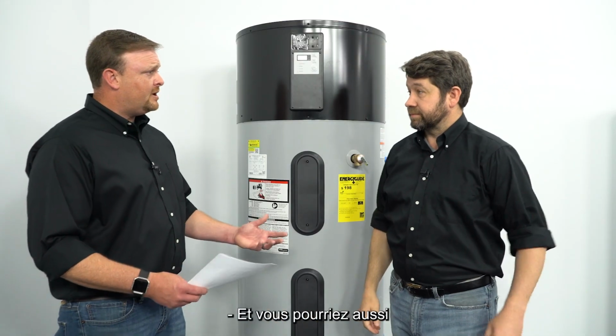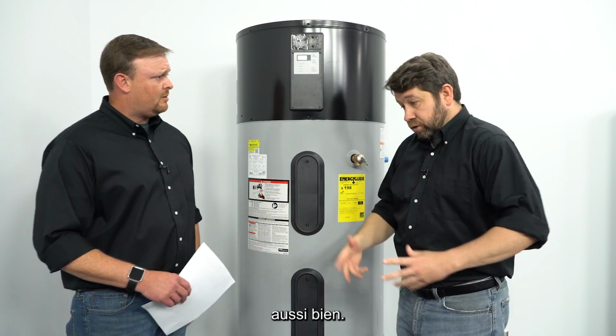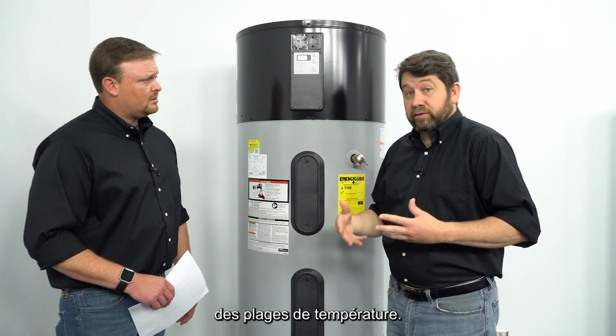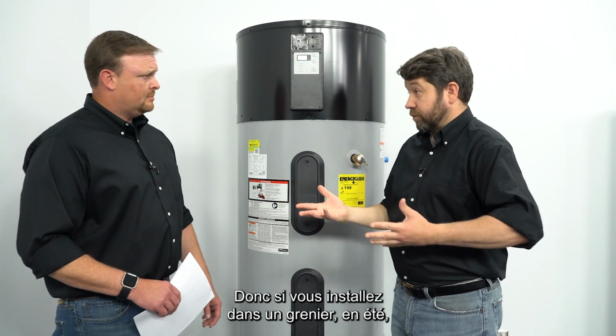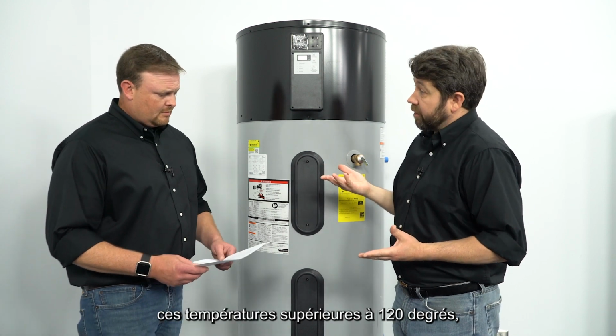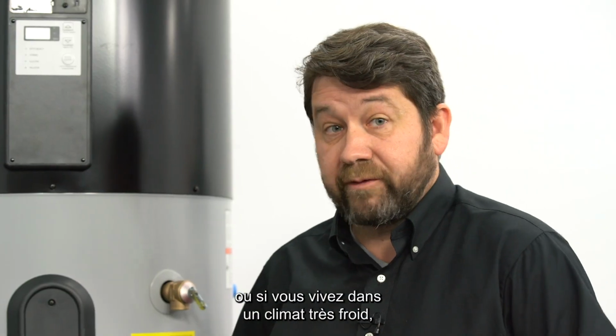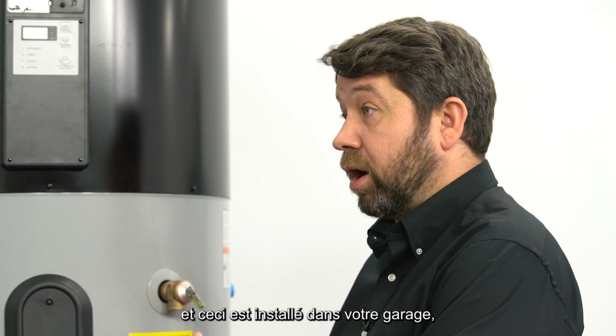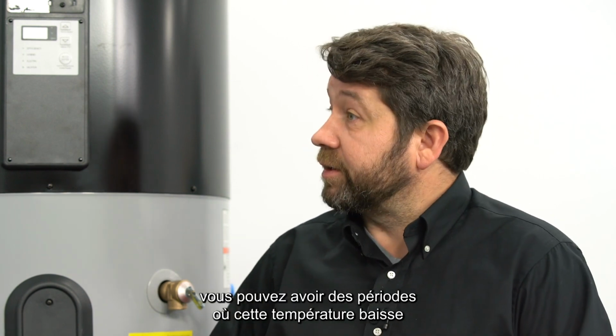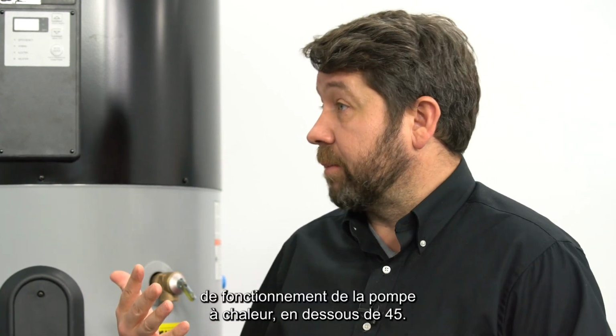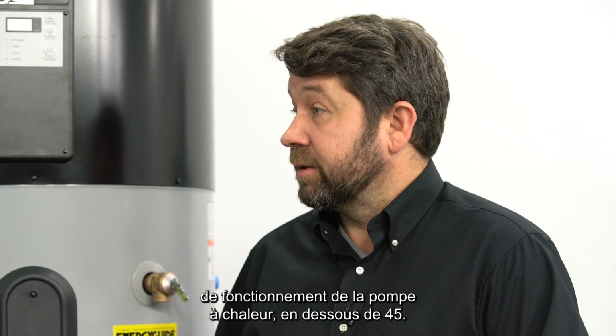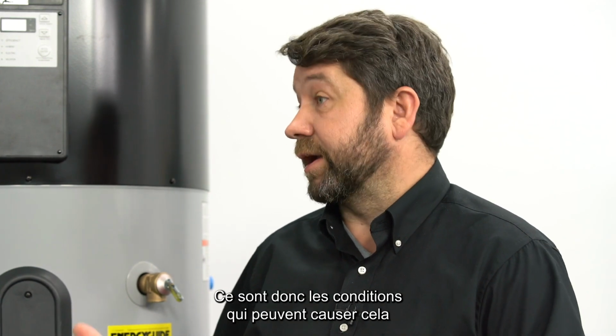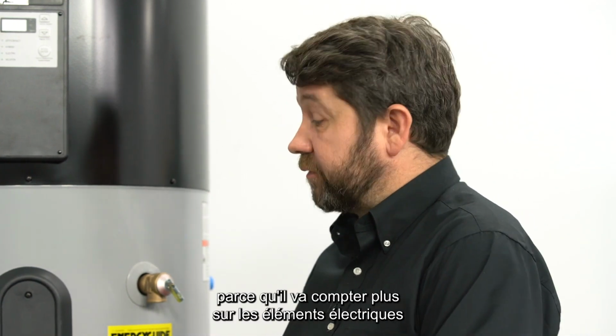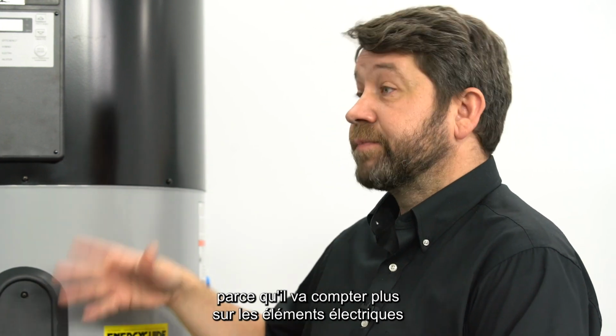And also, you could be outside of the temperature ranges as well. If you're installed in an attic in the summertime where we're going to see those temperatures above 120 degrees, or if you live in a very cold climate and this is installed in your garage, you may have some periods where that temperature falls below the heat pump operating range, below that 45. So those are conditions that can cause this to not operate as efficiently, because it's going to rely more on the electric elements and less on the heat pump.